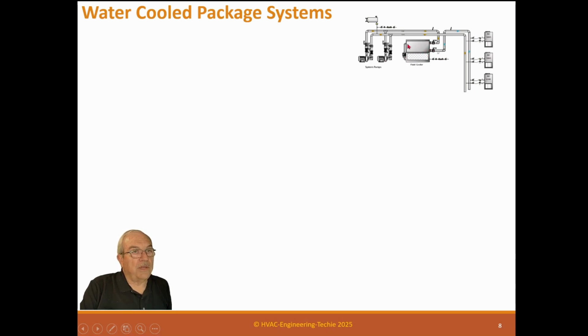And a fluid cooler has a heat exchanger inside here. And this water runs through that heat exchanger and through these heat exchanger bundles, so it's a closed loop, right? And then we have this fluid cooler, which has a water basin in it. It has a pump. So when we need cooling, it turns on this pump and pumps water over the top of this heat exchanger to cool the heat exchanger. And then it has a fan up here that comes on to force draft through that heat exchanger and water to provide much more cooling. So that's a fluid cooler.